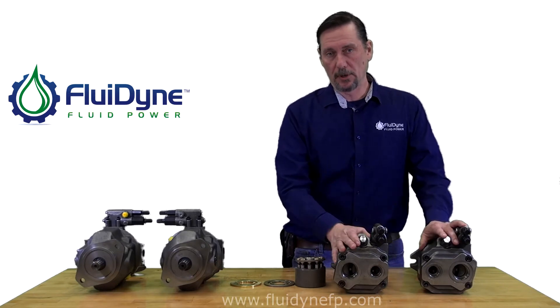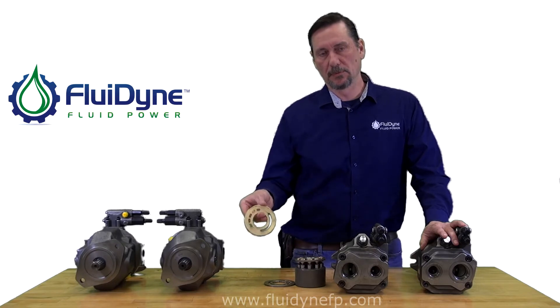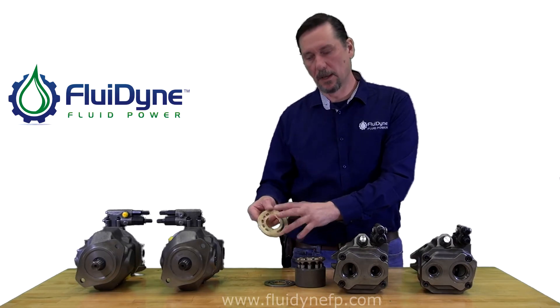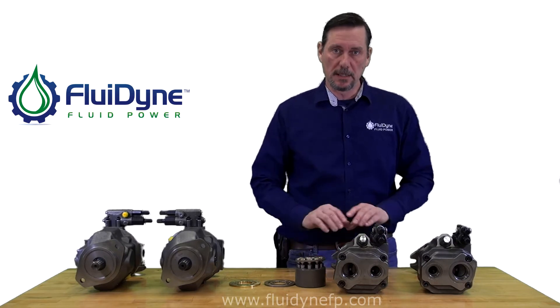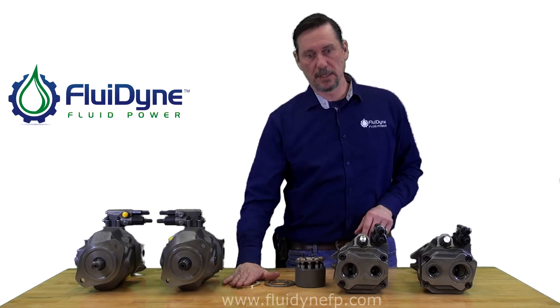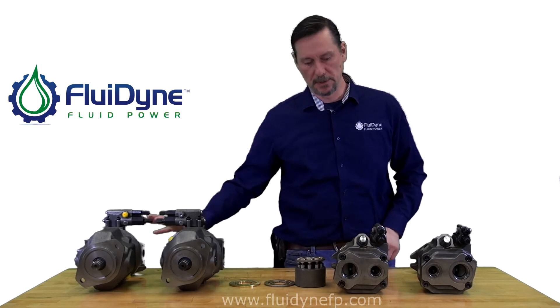If they come in apart, just like the other pumps, the wafer plates will also determine rotation. You can use the same thinking as far as which way the grooves open up. If you're changing rotation on either one of these pumps, there are rotation-specific parts: the wafer plate, the valve block, and the cradle, like I discussed earlier for determining rotation.